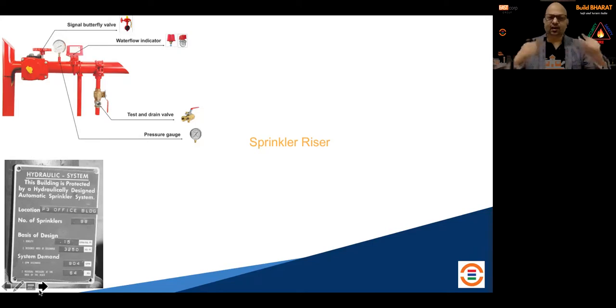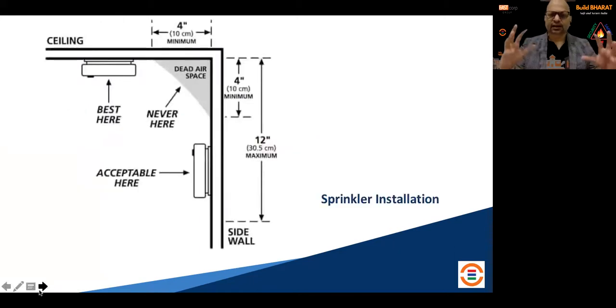So these are all minute issues where you need to see that you are able to achieve it. There are many hotel specific installations I have seen where sidewall sprinklers or ceiling sprinklers have been placed very close to the wall. There is an installation requirement given in NFPA 13 or IS 15105 - what is the minimum and maximum distance to be followed for the sprinkler, if there is an obstruction how do you deal with it, if there is a height constraint how do you deal with it, and whether the spacing will reduce or increase.